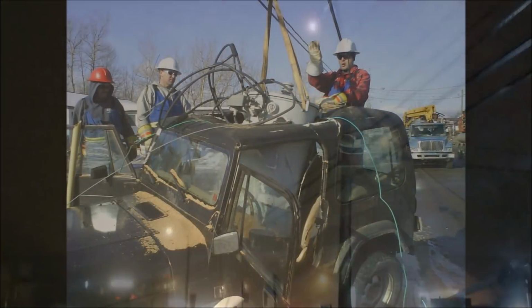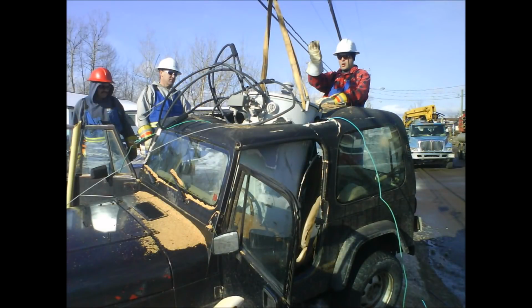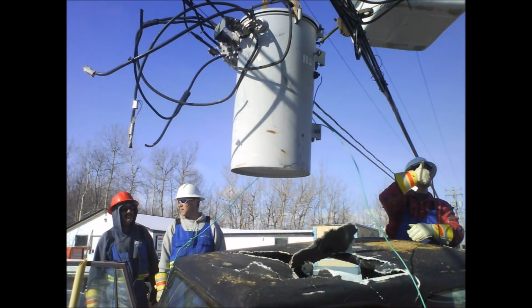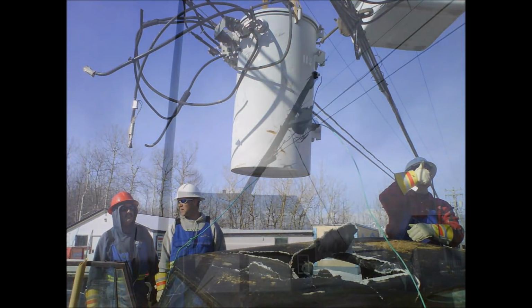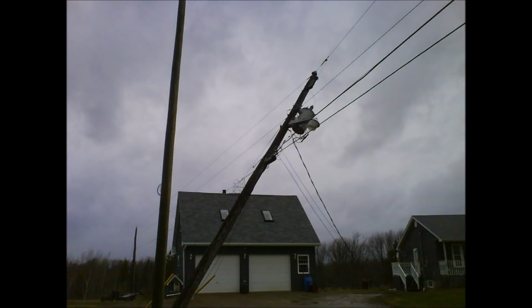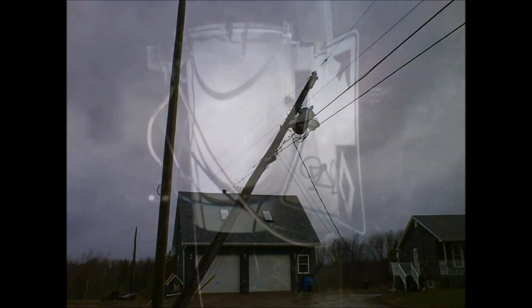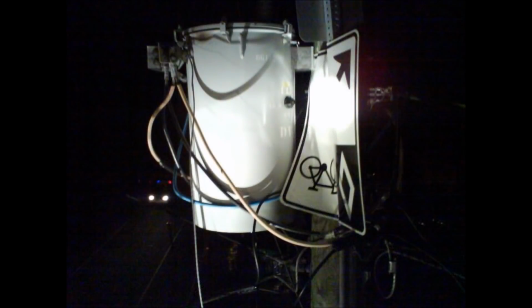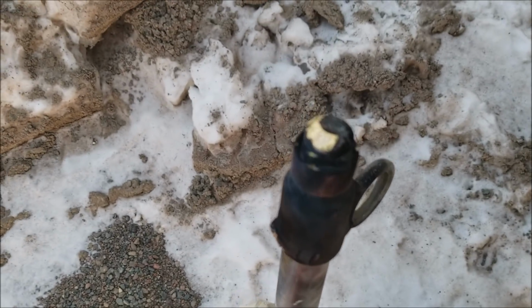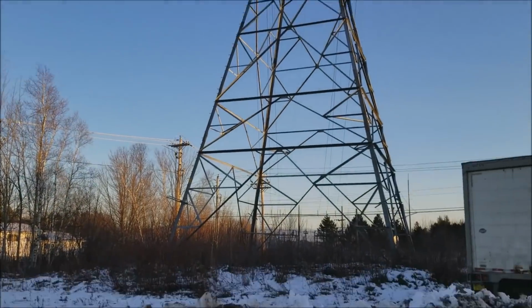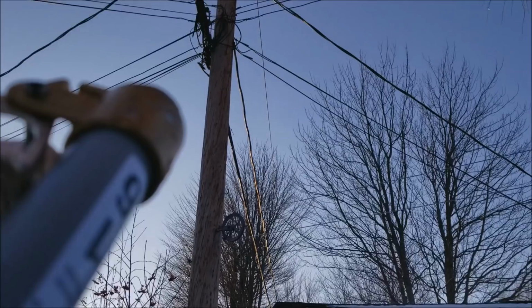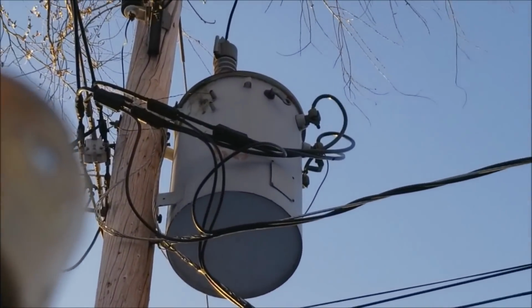And of course, over the next few minutes, I received several reports that a transformer had blown up in the area. Transformers are extremely heavy, this particular one weighing approximately 1,100 pounds. They are filled with copper windings and an environmentally safe mineral oil to help keep those windings cool. The oil transfers heat from the windings to the exterior of the can, at which point it will naturally cool by surrounding air. If the oil becomes contaminated by moisture or other means, it will lose its insulating properties and cause internal arcing, resulting in excessive heat, gas pressure, and very high current. The protective fuse will then quickly blow in order to protect the transformer from catastrophic failure.